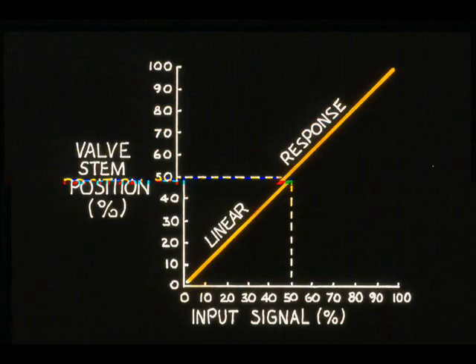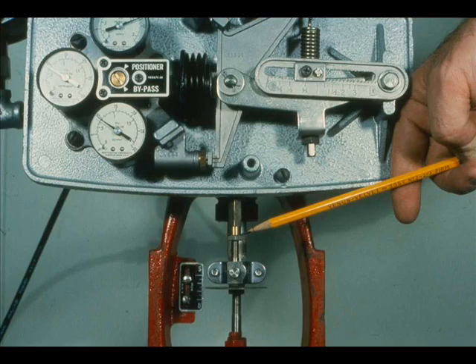For any input within the range of a control valve, there is a resulting stem position. Ideally, the relationship between input and stem position should be linear, and the valve stem should be positioned within three to four thousandths of an inch for the corresponding input.